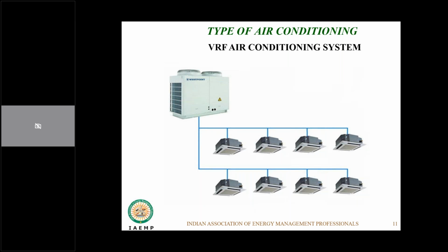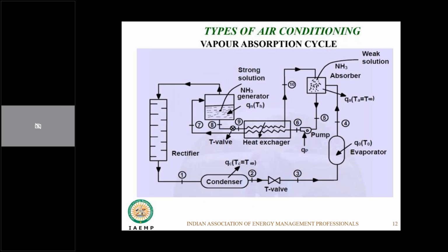Otherwise, you had a serious problem of oil retention in your evaporator, and compressor failure problems would increase. All those problems were eliminated when we had the VRF system, because these are designed for having the condenser unit put on a terrace, and you can have a vertical height of almost around 60-70 meters and a horizontal distance in excess of 100-120 meters. Okay, so this takes care of our compression system.